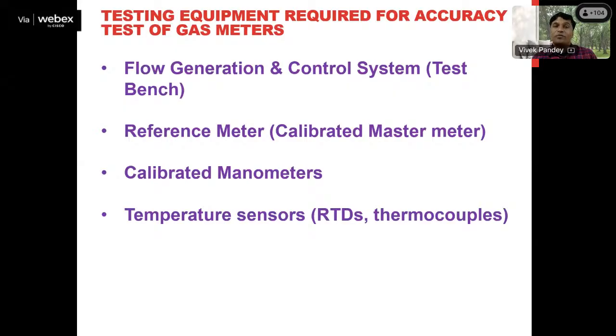That means there should be a flow generation and control system in the testing setup. Then there should be a reference meter, that is, a calibrated master meter, which must be checked and calibrated by an authorized agency, authorized by the central government, obviously. And there should be calibrated manometers, because during the testing process, whether for reproducibility, repeatability, or accuracy test, the rated operating condition must be ensured. Rated operating condition means the desired pressure range and the rated temperature value should be ensured. So these associated parameters should be measured by calibrated instruments. Pressure should be measured by a calibrated manometer. Temperature should be sensed by a temperature sensor, which should also be calibrated. So this is the basic setup, according to me, which is required.